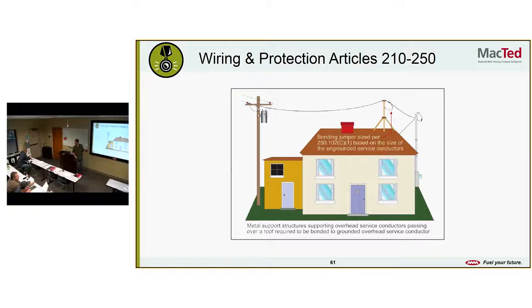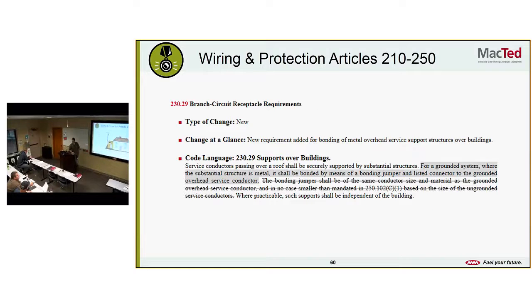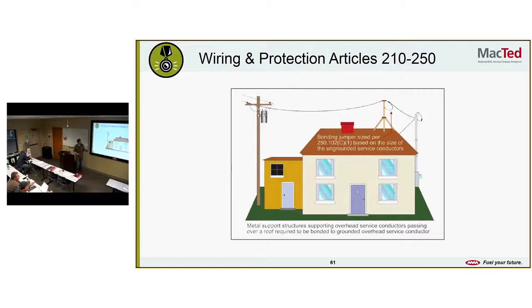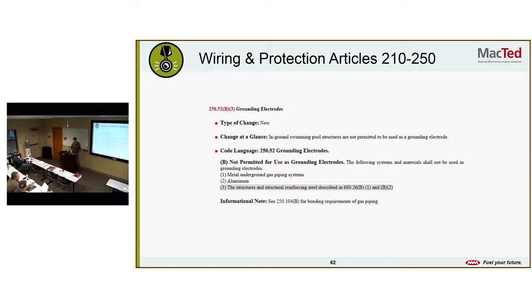Metal structure over a building. Yeah, exactly. Any questions on that? Grounded systems. Do we want to reread that last one? For grounded systems where the supporting structure is metal, it shall be bonded by means of a bonding jumper and listed connector to the grounded overhead service conductor. Okay? All right. Metal pole buildings, stuff like that.